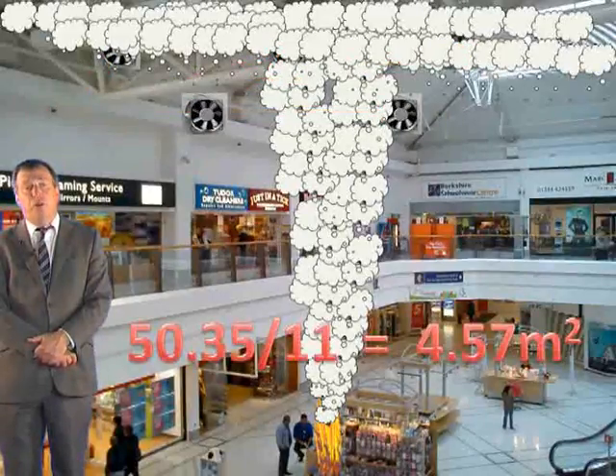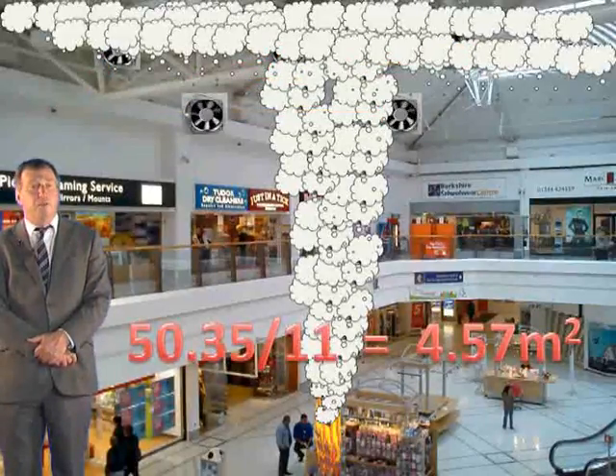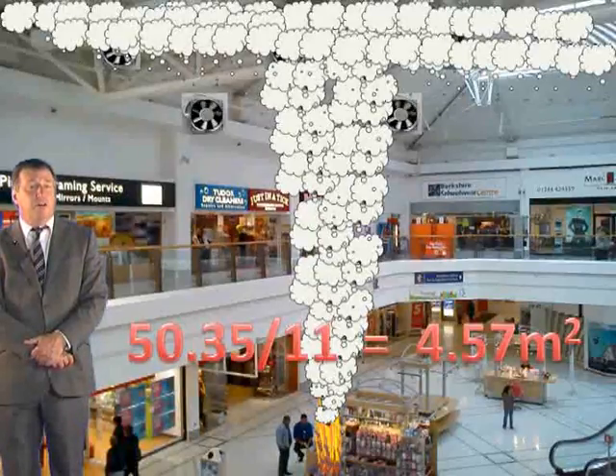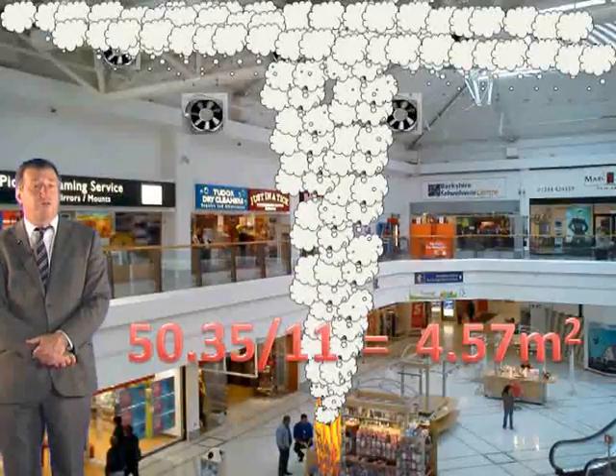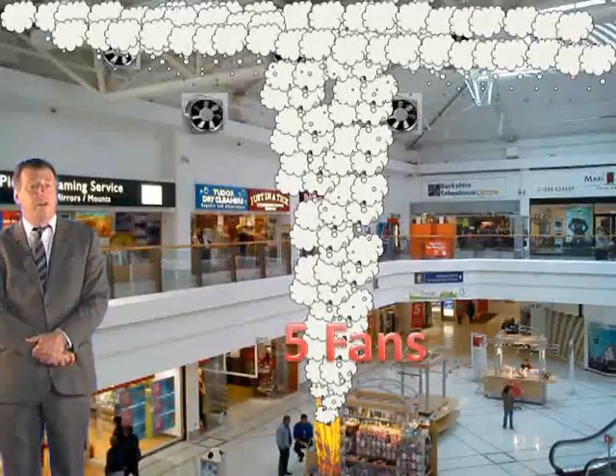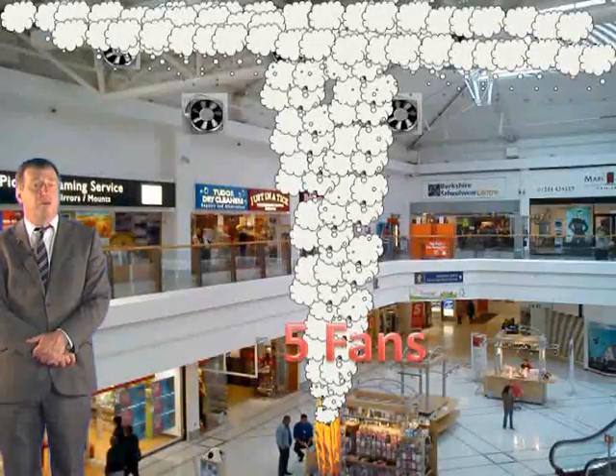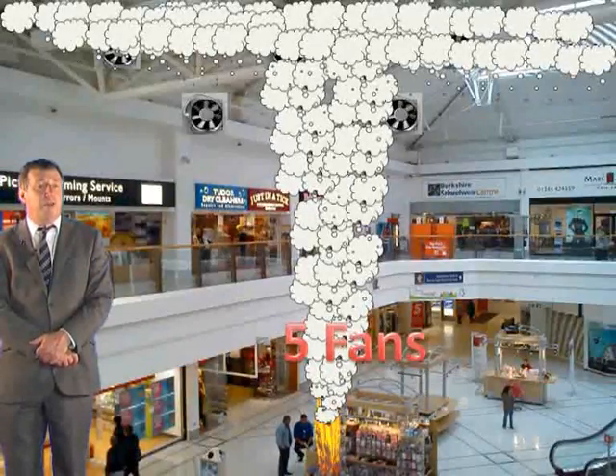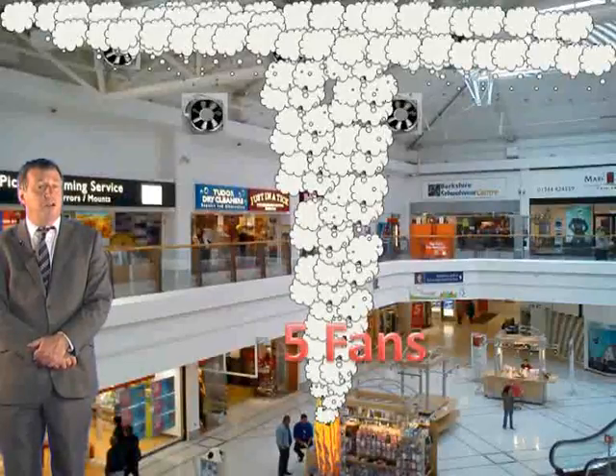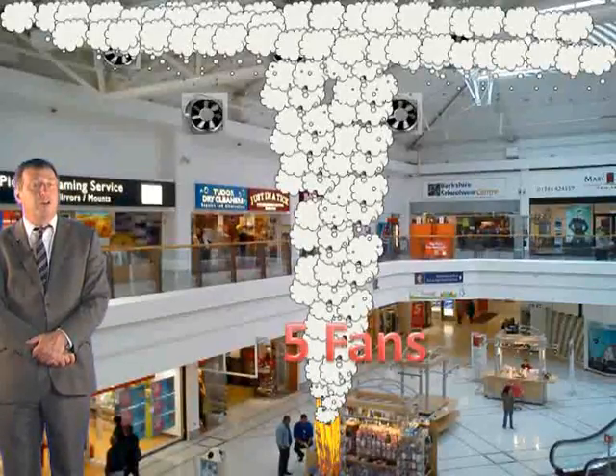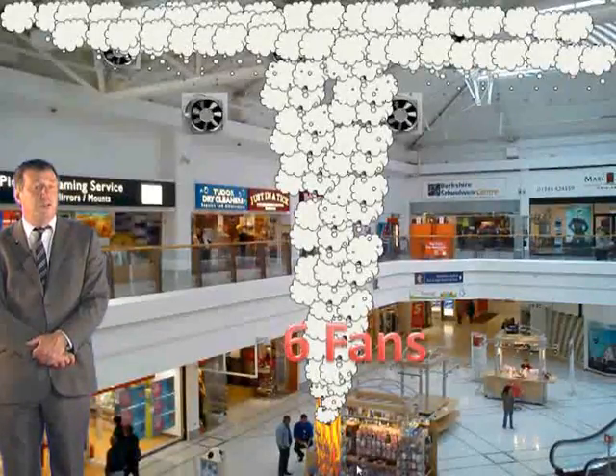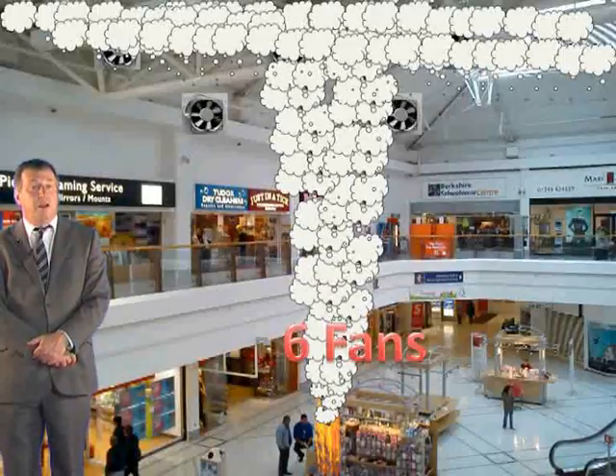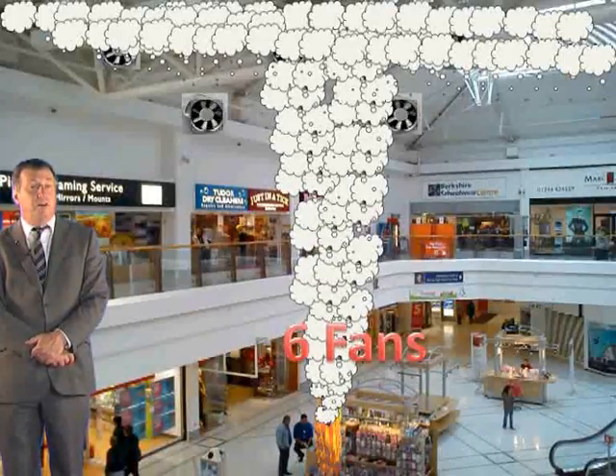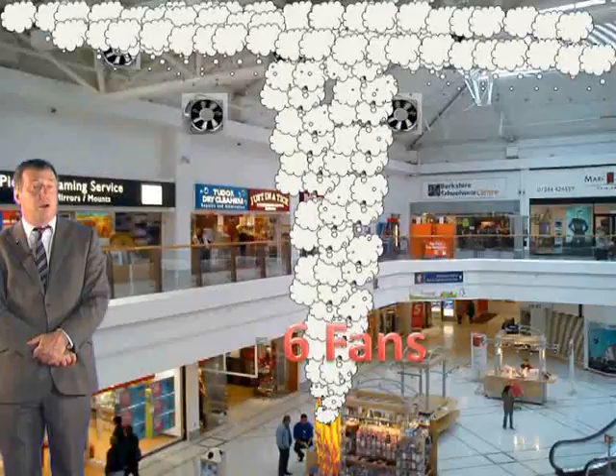Well, 50.35 divided by 11 is somewhere between 4 and 5. We don't have to calculate it precisely, as we have to round it up anyway to 5. So we round the answer up, and 5 is the number of fans that are required. But then we have to add one fan because we might lose one to the fire. And so the result is that we shall need 5 plus 1, which equals 6 fans, each with a capacity of 11 cubic meters per second, and in each reservoir.